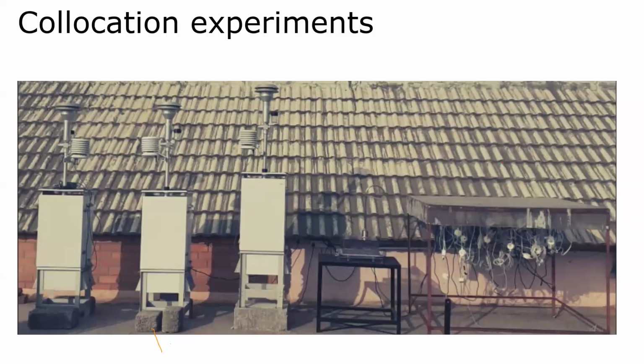This comparison is called field collocation, meaning installing the sensors side by side in the field, that is, in the ambient atmosphere. For example, if you're measuring in Delhi, it's better to do the co-location there too, to test accuracy and, if needed, derive a correction factor to apply to the low cost sensor data for meaningful results. In this photo you can see three BAM instruments, beta attenuation monitors, specifically BAM 1022 models, which are standalone monitors.